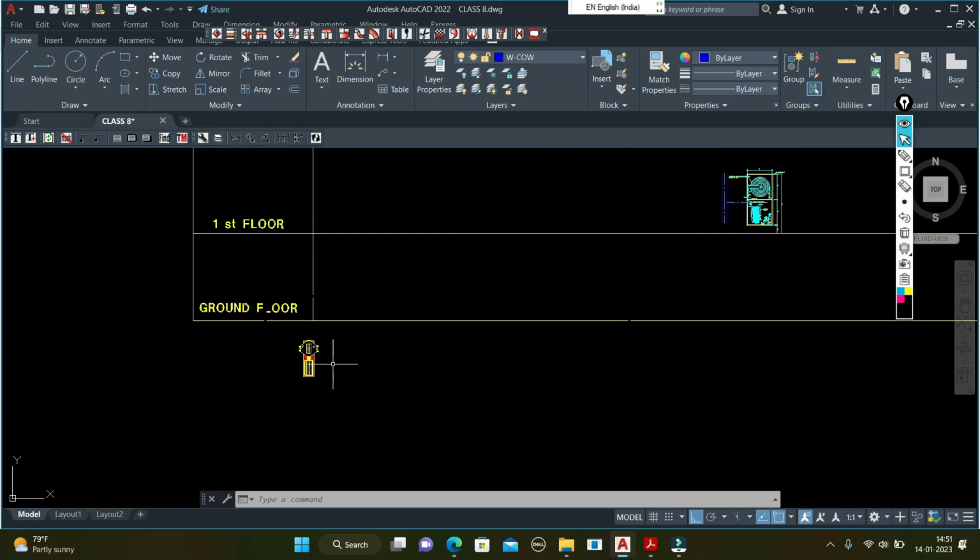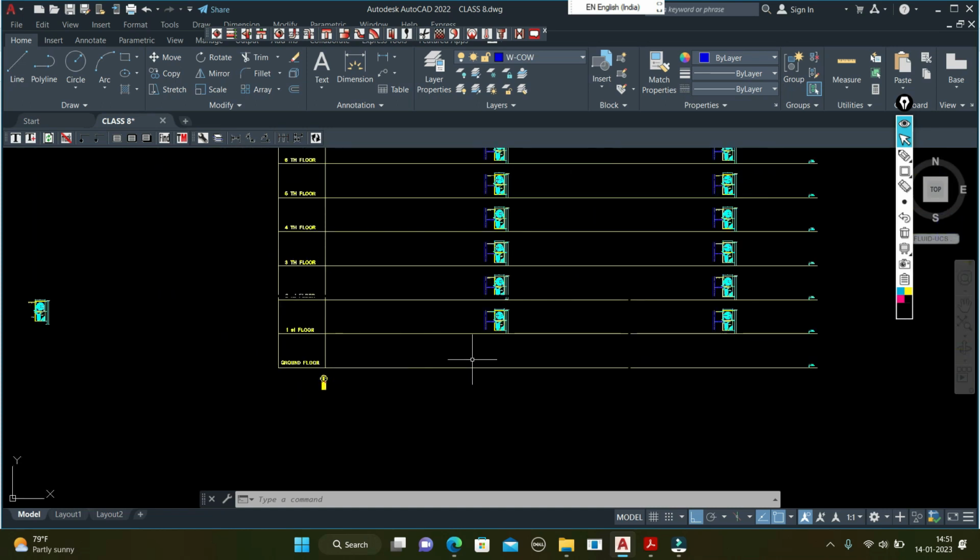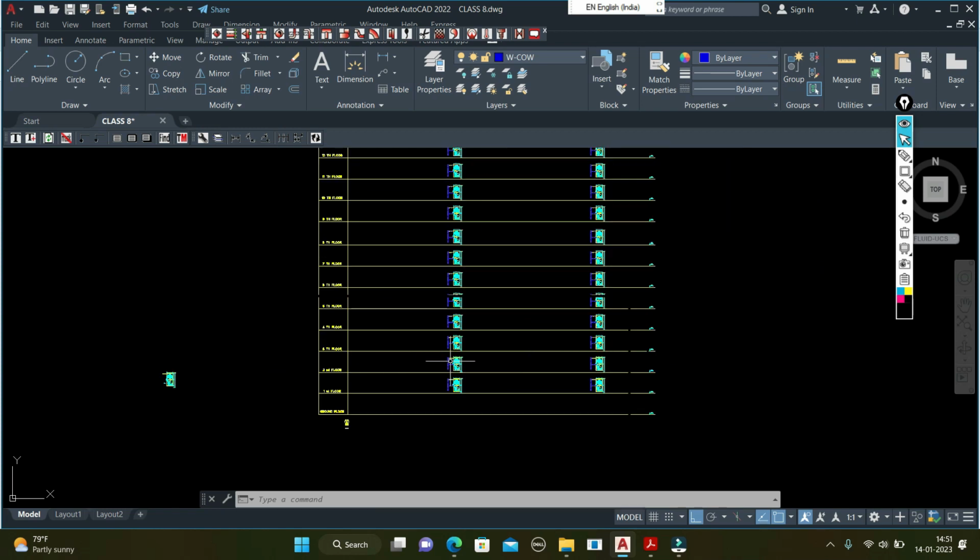Okay, and this is the pump. So we don't know the size of the riser. Okay, and in a mid-rise building we take the header, one header, and the riser, that one is called a stand pipe. And from that one header we also take the pipe for the sprinkler system on every floor. Okay, each floor, and place the zone control valve.